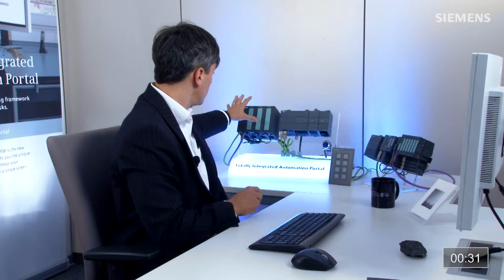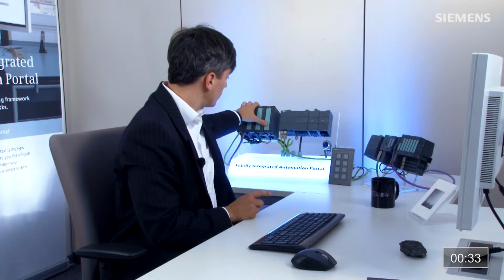So we have the 315 master here, and what I need to do is make the physical P1 to P2 connections for all the devices and have them done exactly correctly. So ultimately, choose the master's first connection and take that to the KP8, and do the exact same thing from the ET200SP to the KP8. So now what I've done is a physical connection from this master 315 to the KP8 and from the KP8 to the ET200SP.